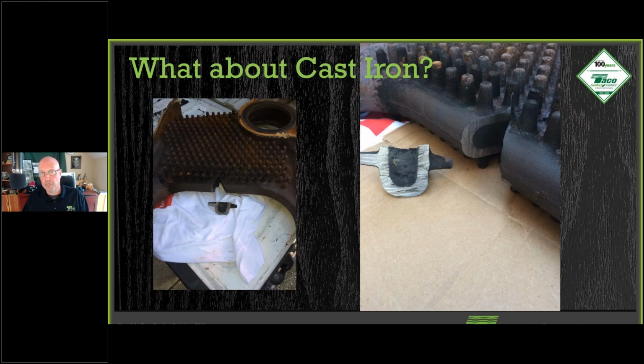You start looking at this boiler here. Here's your cutaway. Look at that. Completely plugged solid. If I remember correctly, this is about a 4-year-old boiler, and it's plugged solid down here at the bottom, where the fire is. We're wondering why we're not getting heat transfer and what's going on. So they cut it open and took a look, and we're looking at a plugged system again, from keeping that dirty water in the system and not cleaning it beforehand, or not draining, purging and treating the system itself.